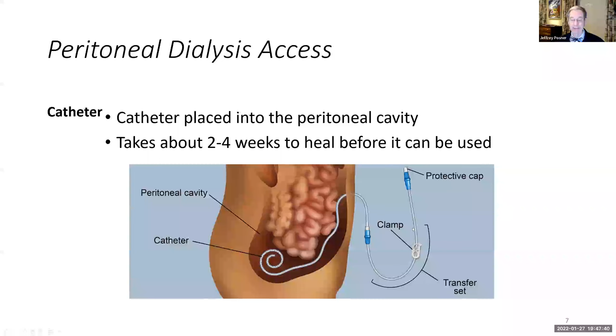Now, an extra bit of detail in this diagram is you can see that there's the complete catheter. The catheter ends here, and we typically connect to that a transfer set that is then used to connect to the dialysis system. And we're able to place a clamp here on the system to prevent fluid from leaking in or out.